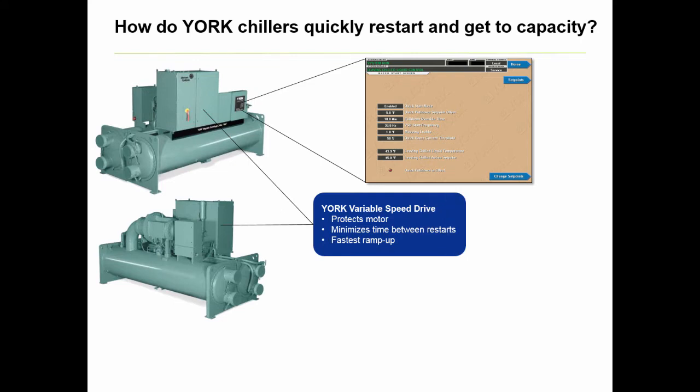Second, the YMC-squared utilizes a standard York OptiSpeed variable speed drive. This provides maximum motor protection during startup and operation, it cuts down on the time between chiller restarts, as we saw in the video, and when directed to, it can ramp up the speed multiple times faster than any other manufacturer's design.